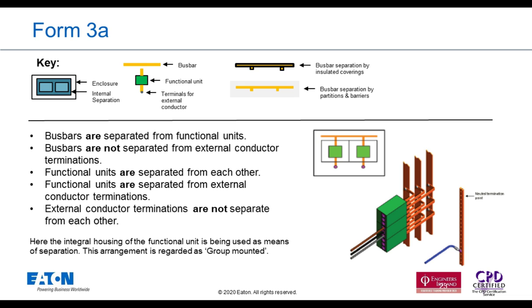So here's 3A. The main bus bar is separated from the functional unit using the enclosure of the protective device, and again the casing of the protective device is also being used as a barrier between each functional unit. This type of arrangement in the market is known as group mounted.